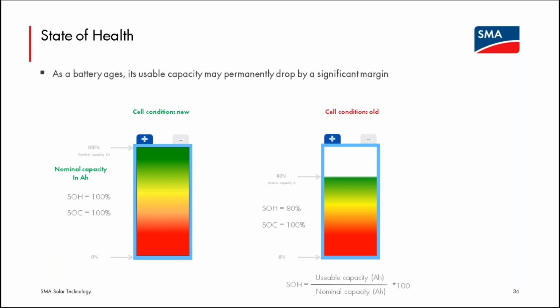As batteries age, the state of charge, that is the amount of charging they can do, might reach 100% before the nominal capacity at day 1 is reached. That is, the battery ages and it becomes, in essence, a smaller gas tank. It can't hold as much fuel, as much energy as it did on day 1. But there's no point in continuing to try to dump current into it because it can't hold anymore. So this state of health metric is monitored also by the Sunny Island. So if the 100 amp hour battery bank on day 1 can only hold 80 amp hours 5 years down the road, the Sunny Island is smart enough to know that once 80 amp hours of energy have been put into it, its state of charge is 100% because the state of health is only 80%. And there's no point in continuing to try to charge it. So while it is driven by state of charge, it's smart enough to adjust based on state of health that an aged battery can't quite hold as much.